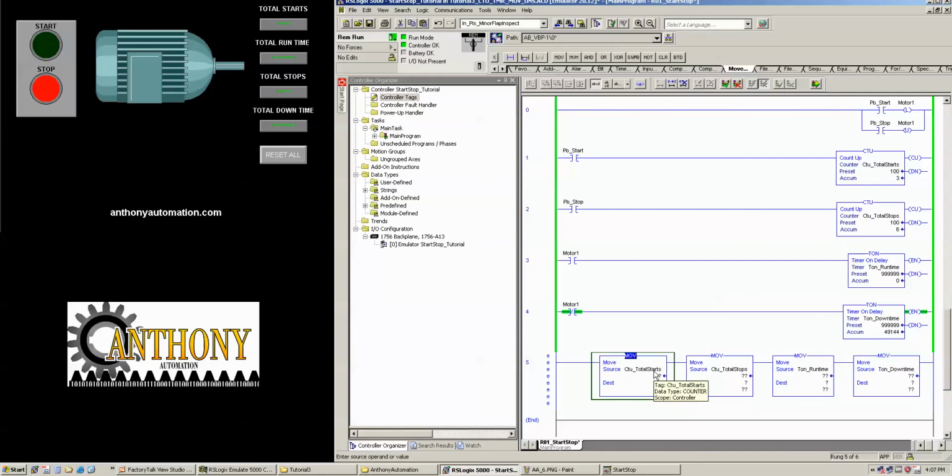Now, I was on the phone one time troubleshooting a machine with a guy, and he was asking me if the move function actually made the equipment move. The move function does not, it's not a move command. It only moves data from one tag set to another, but it overwrites the data in the other tag set. So in other words, if you want to take this value, which right now is 3, I'm sorry, we got to say accumulated for all these guys.